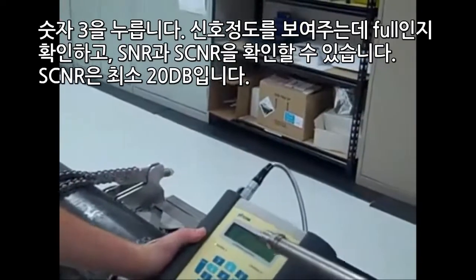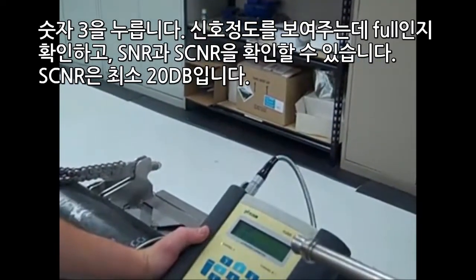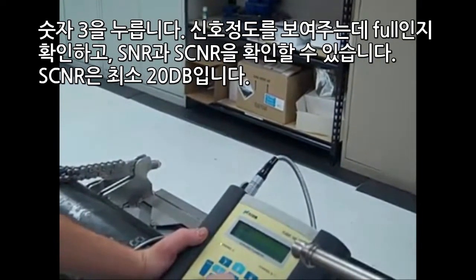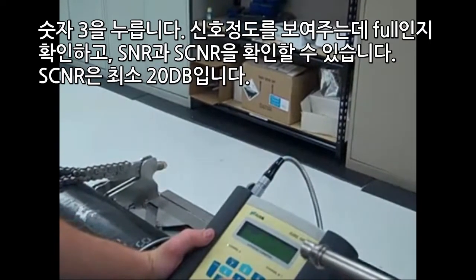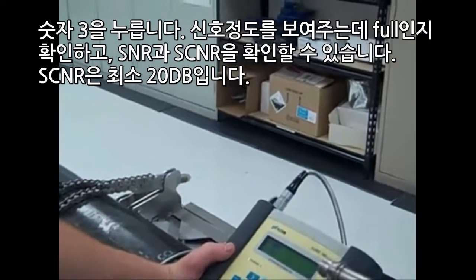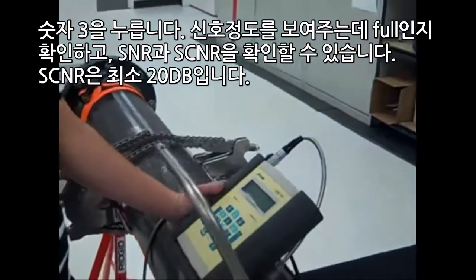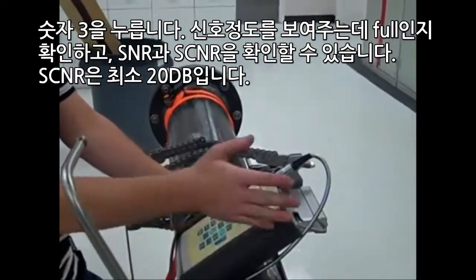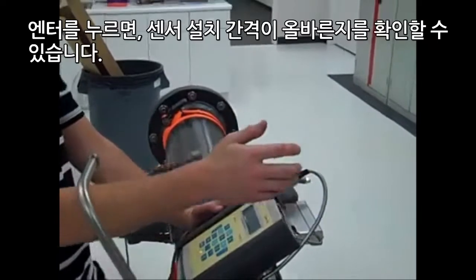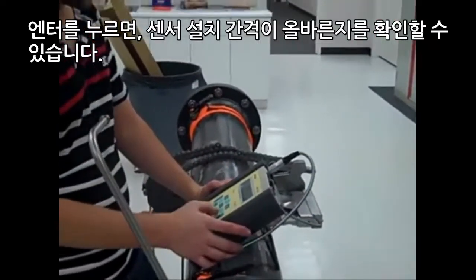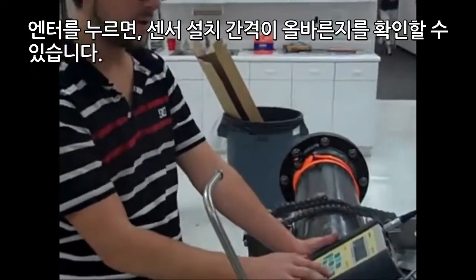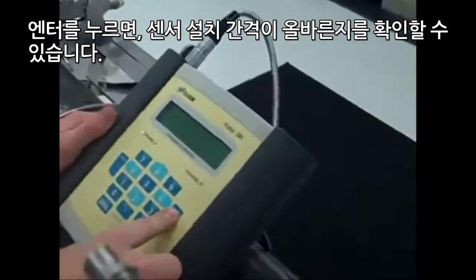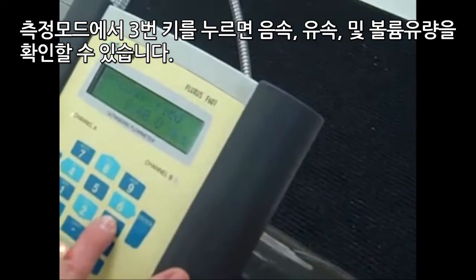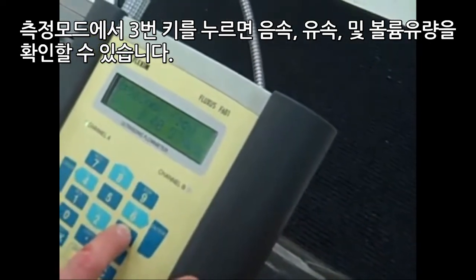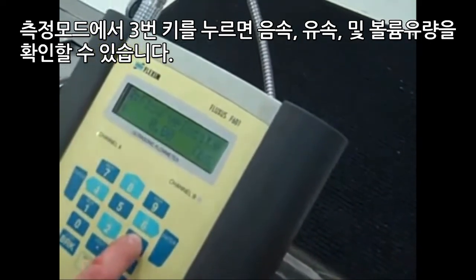Press enter. You're going to press the number 3 key. It's going to bring you to your quality. You want to make sure that's full. And then you get to your SNR and your SCNR. SCNR is what we're looking at here. Looking for a minimum of 20 dB. And that's what we have, 35 dB. Pressing the enter key, this is where you're going to make sure that your transducer distance is perfect. And using your 3 key in the measurement mode, you want to check your sound speed, and this is where you get to see your flow velocity and your volume flow.